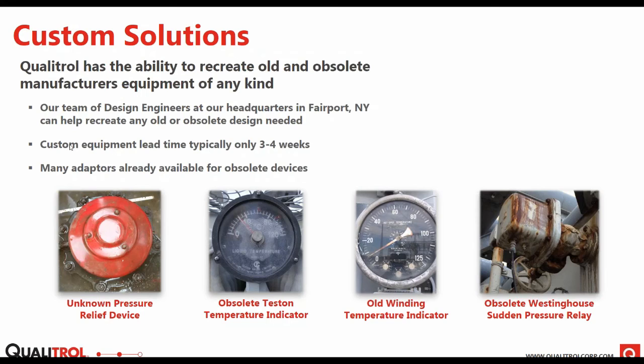But if we did need to go for a completely new design, our lead time on custom gauges is typically only 3 to 4 weeks. And like I said, many of the adapters are already available. This is a big replacement. A lot of these old Westinghouse sudden pressure relays are getting old, and it's a quick replacement for the sudden pressure relay.